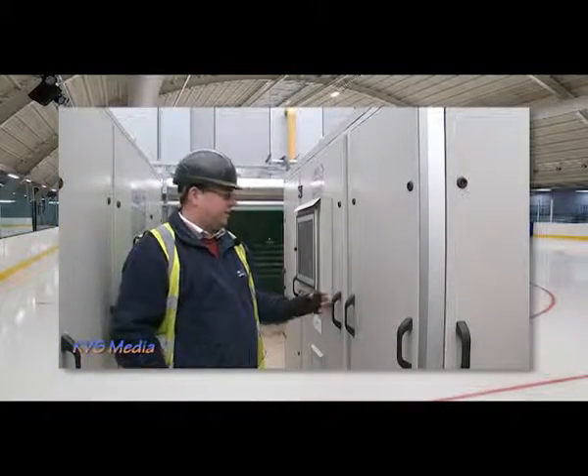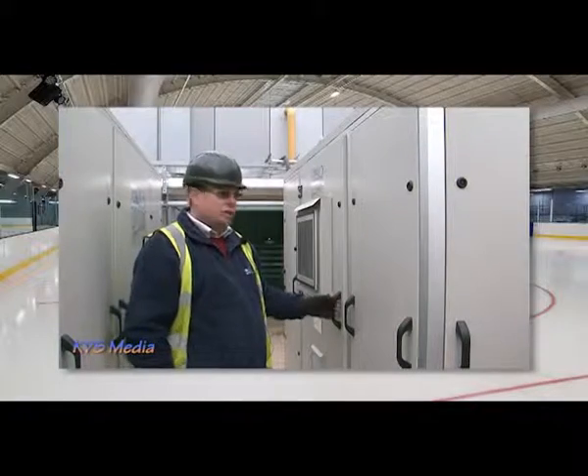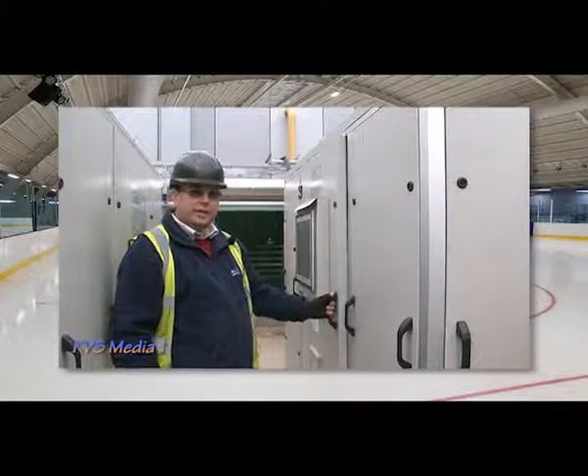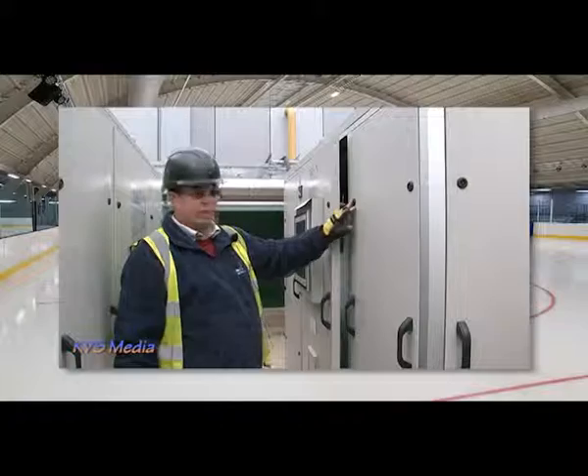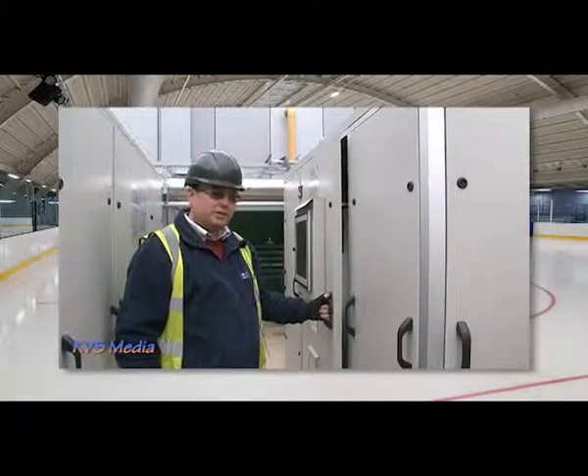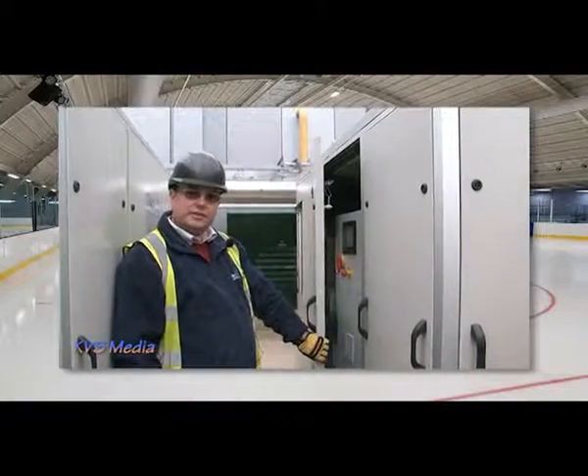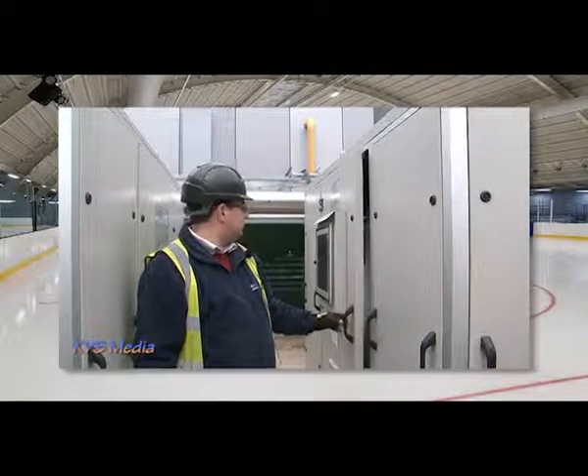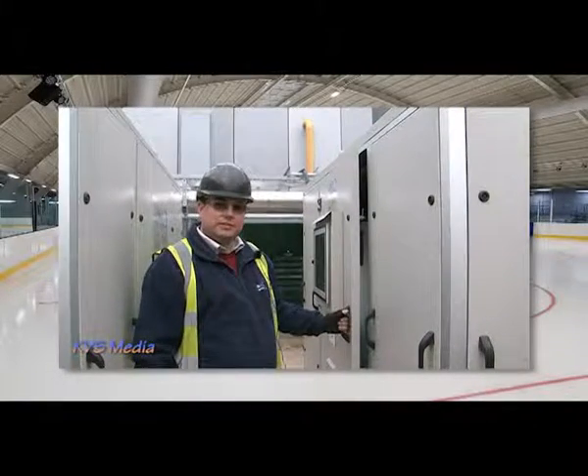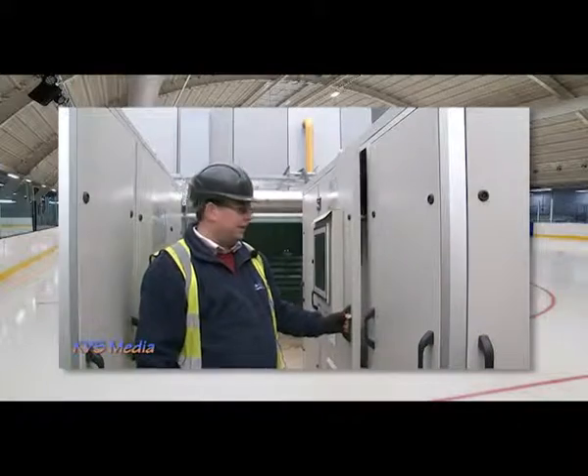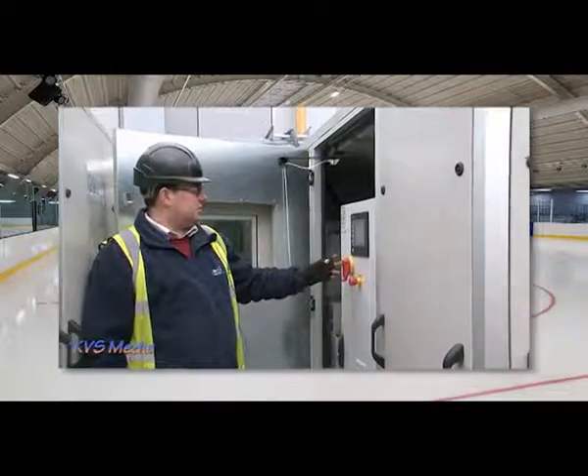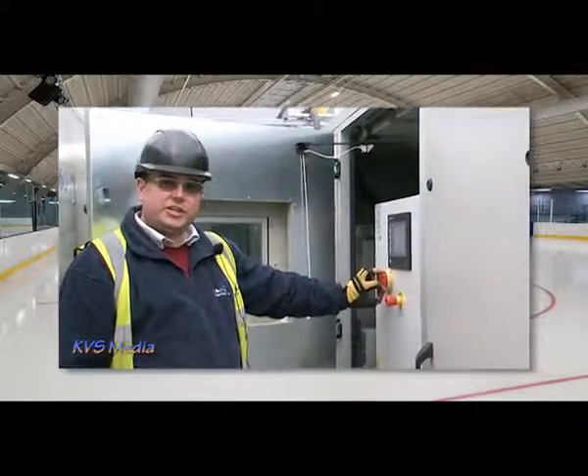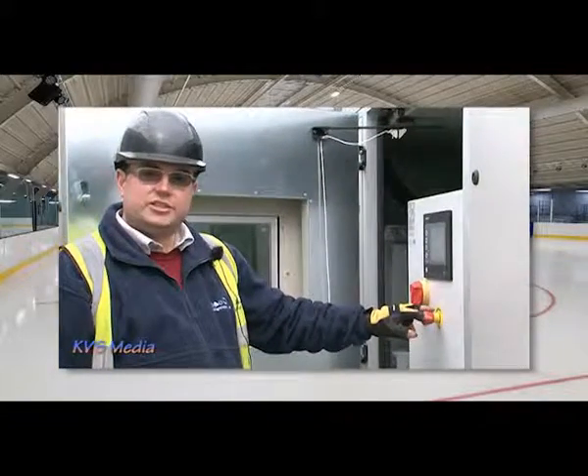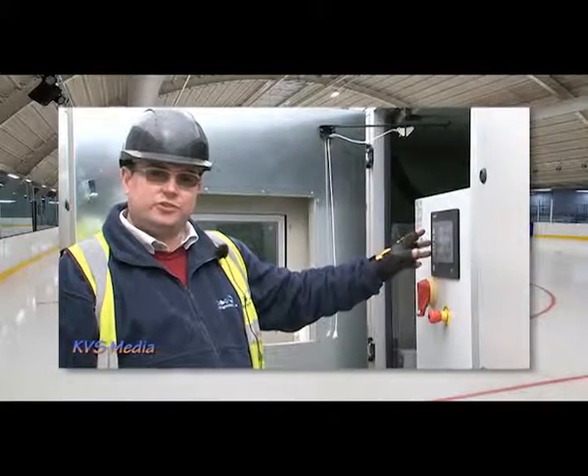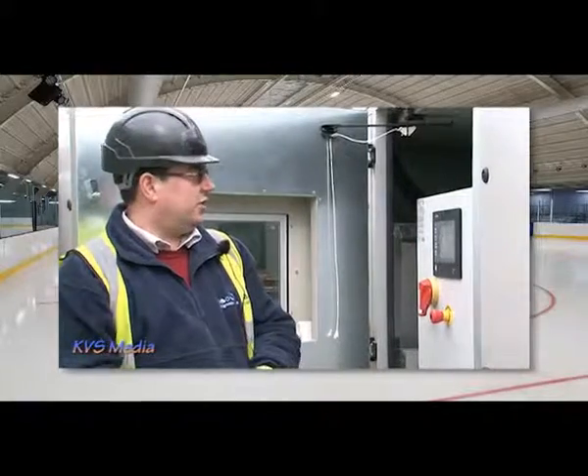So now we're at the compressor end of the chillers. Following on, again, all these panels can be opened with a standard utility service key. Within these there are small control panels which can be operated and reset the chillers when needed. As I said, isolation switch here for the whole chiller, an emergency stop, and then a touchscreen controller for the operation and control of the chillers locally.